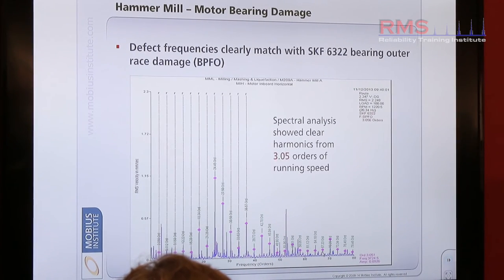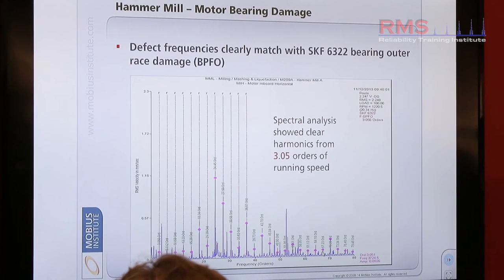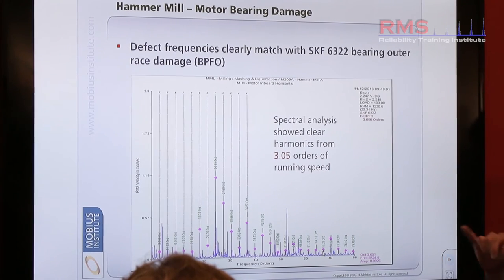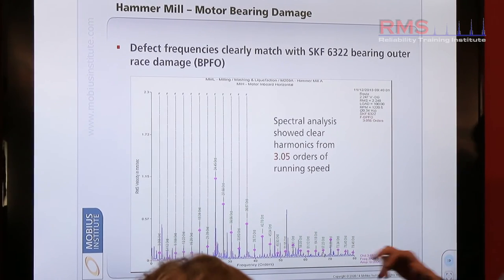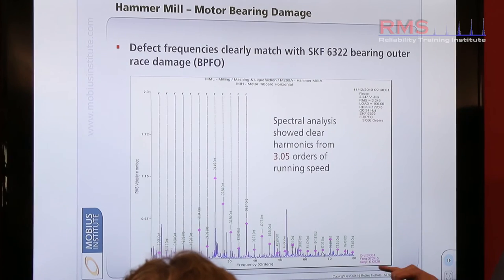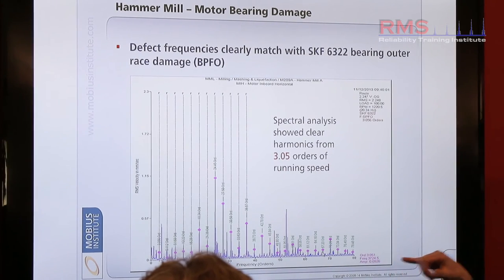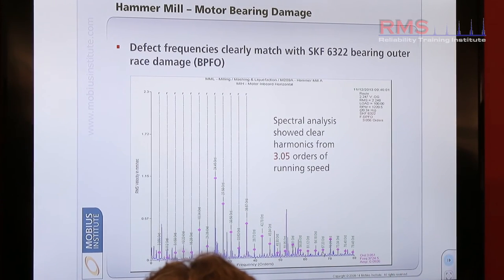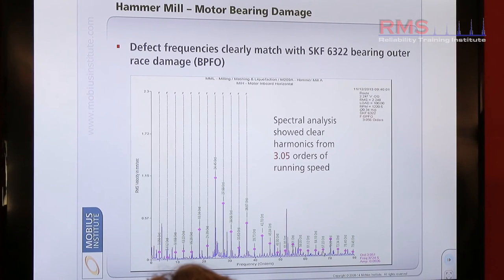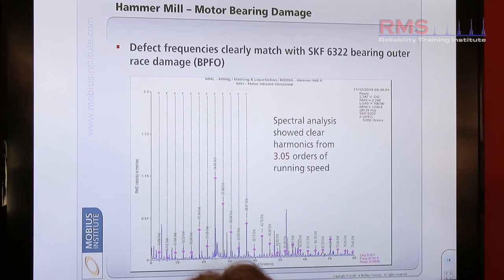The point is, what is the rate of those peaks? What is the spacing between them? Well, the driving frequency — the first one — is at 3.05 times speed. So let's just round that up to 3.1 times the speed. Not three, but 3.1 shocks per rotation.